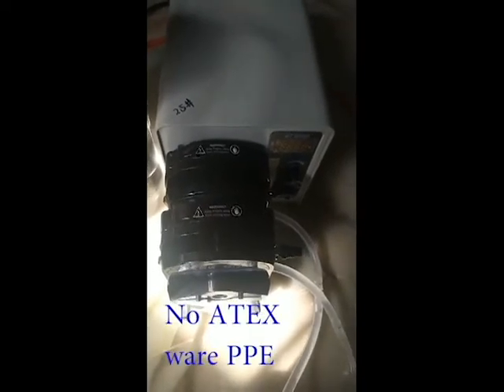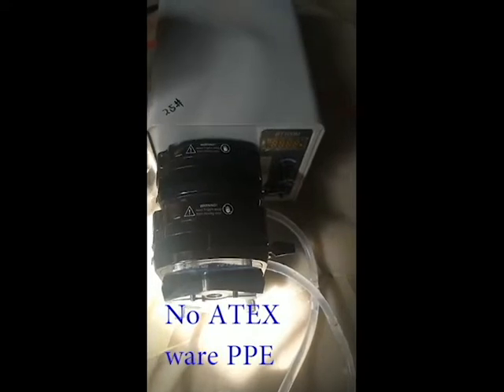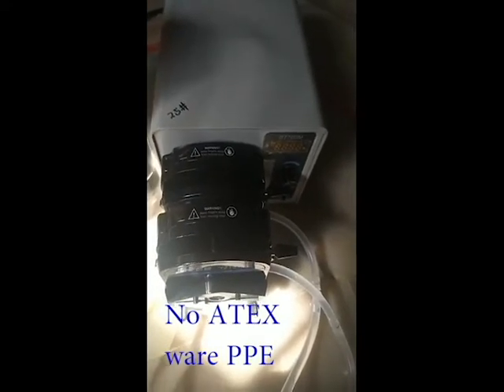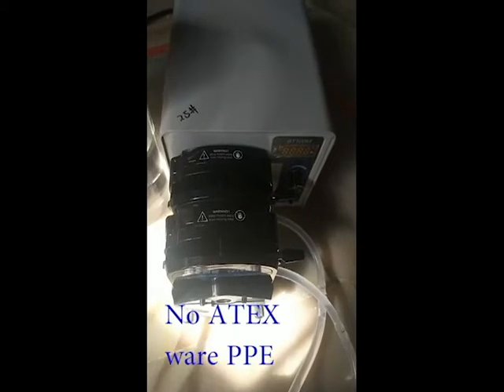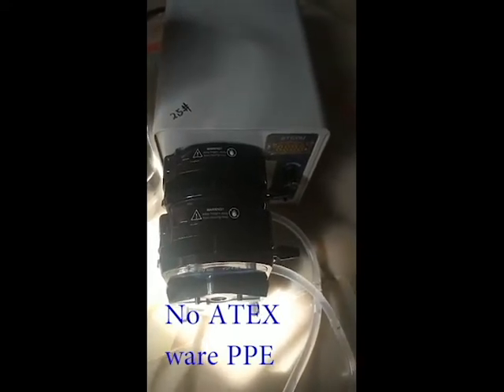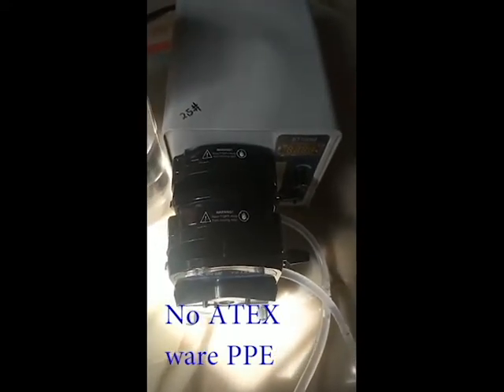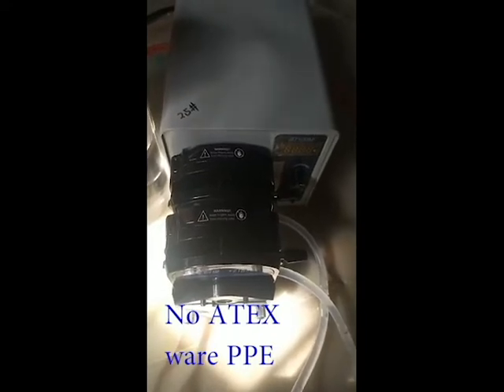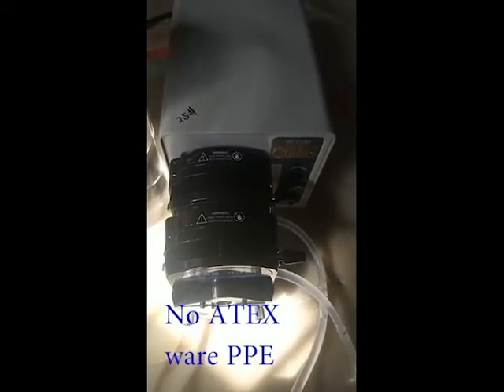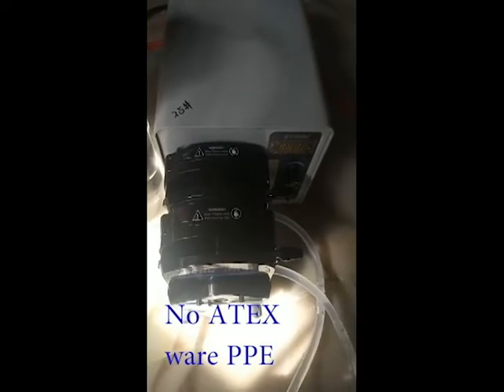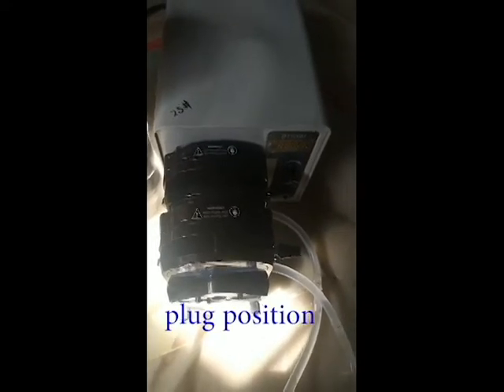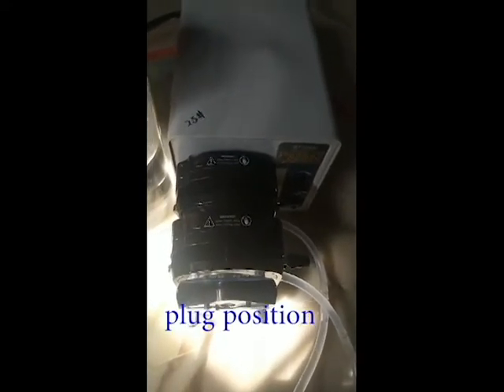85 milliliters per minute. And another thing, this pump is not designed to be explosion-proof, so the system should be used in a common environment. You cannot use it in high explosion risk conditions, so pay attention. And when you use corrosive chemicals, toxic chemicals, or poisons, you must wear the necessary PPE and follow your safety requirements. And finally, put the power supply of the pump close to your operation, and when any emergency happens, you can switch off the power immediately.